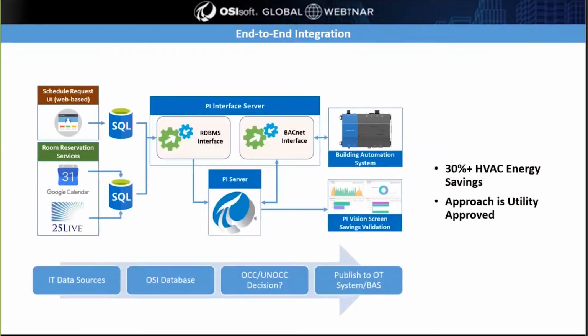On the left-hand side we had that IT silo of room reservation information; on the right-hand side we had the automation system, but there was no connection. Now we're pulling that data from the cloud-hosted sources, bringing it through to the PI system, and sending commands from the PI system to the automation system—ones and zeros to the terminal boxes in individual spaces to make them go occupied and unoccupied. With this approach we've seen over 30% HVAC energy savings, which is expected if you're familiar with how HVAC is normally scheduled.